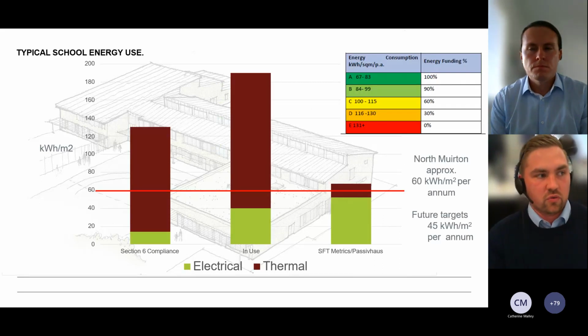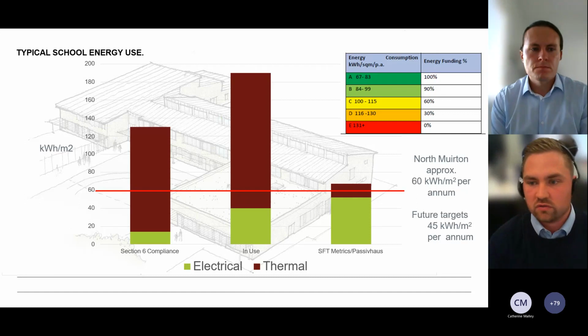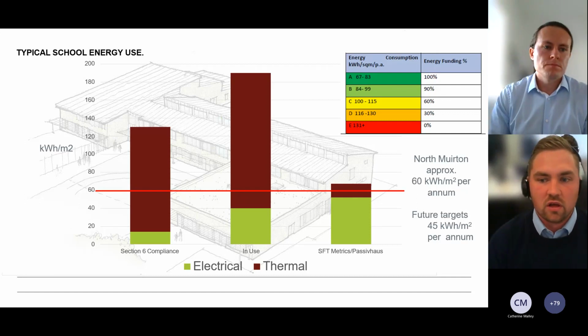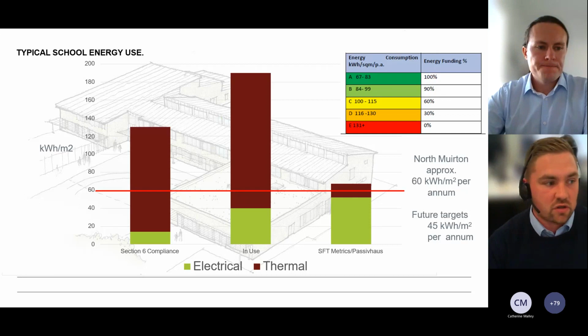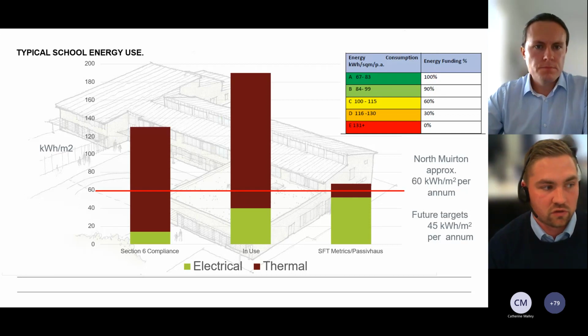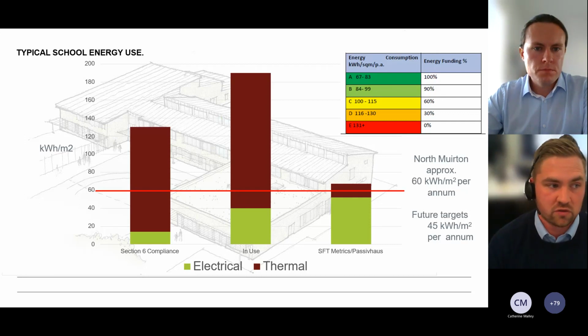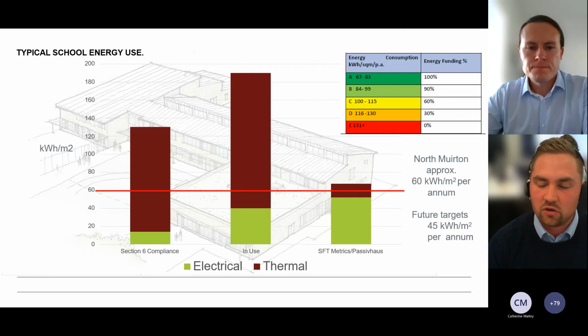Going on to the actual energy usage, the table on the left is a Section 6 compliance, which is how we normally run our projects up until now. There's a lot of thermal demand, small electrical demand. But when you look at how we would then model a TM54, your in-use energy model, we notice a large increase in electrical demand, and the thermal demand also increasing because we're putting in actual operational usage profiles.